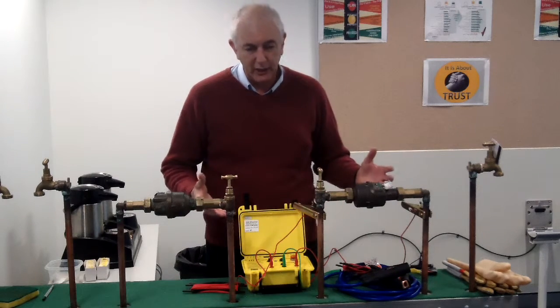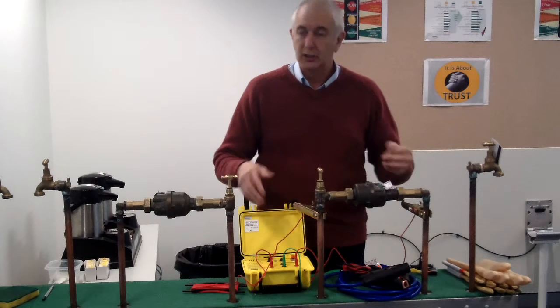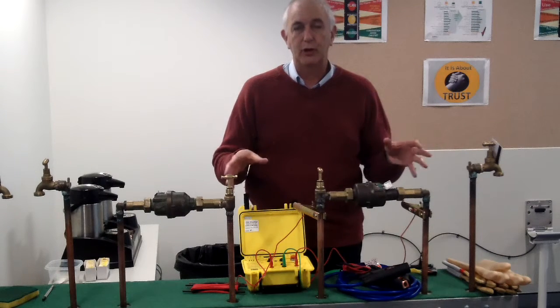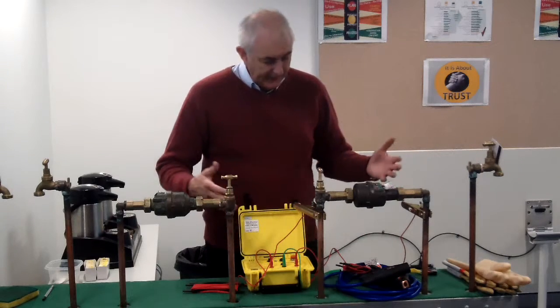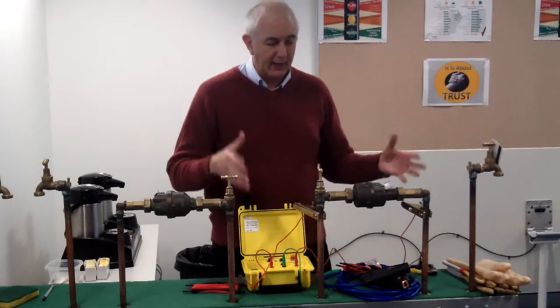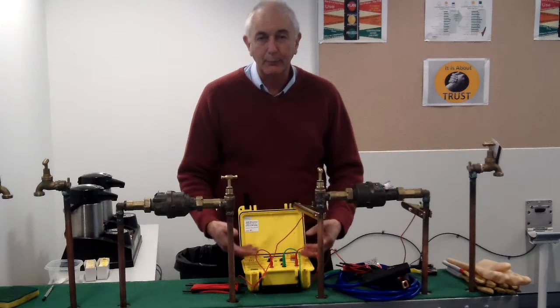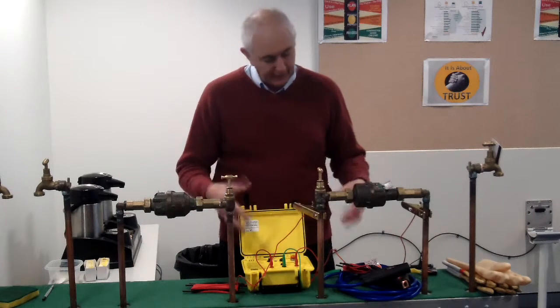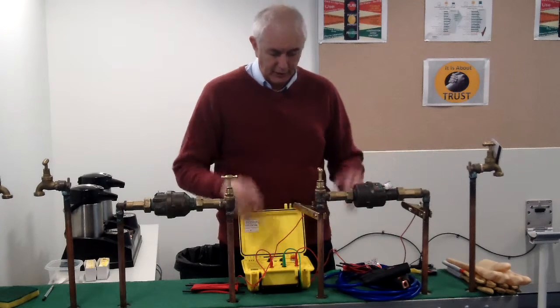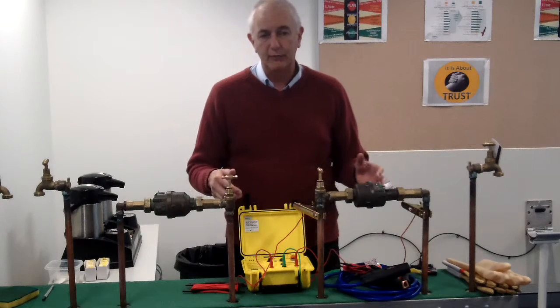That's a good safety feature. If you're working on a site, you move away for a minute, you come back and this thing's flashing — don't go near the site. Report it and treat it as live. So that's how we use the PlumGuard on site. You need to test it before every job, and the full setup — putting it on site and turning on the unit — should take less than a minute.